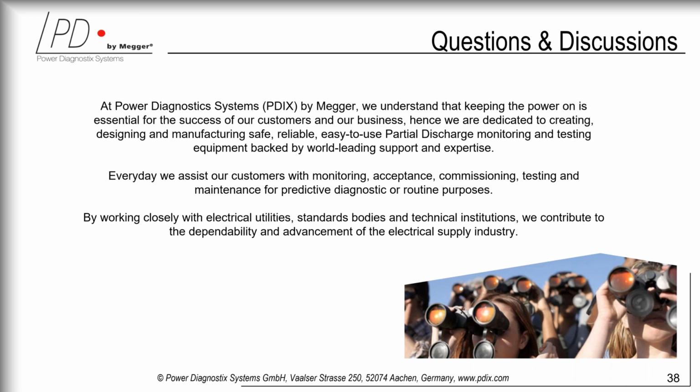So just basically by analyzing the pulse shape and where you're testing from, this will help you to identify the type of defect and where that may be. And again, looking at the phase resolved partial discharge pattern, or the PQN pattern that Mihai had shown on several of his slides, that really gives a good indication, like I said, of the type of defect and where that may be. And that can be followed up by other testing methods, again, maybe acoustic, to actually try to find out where that partial discharge defect may be.